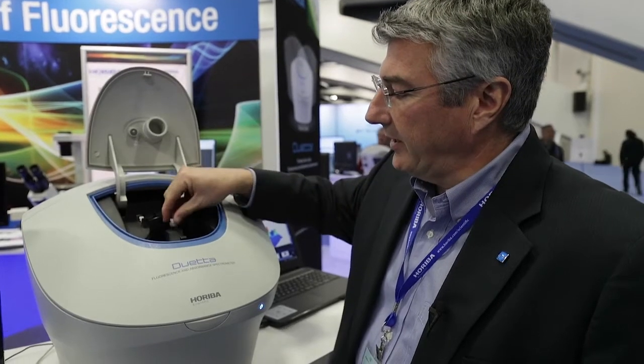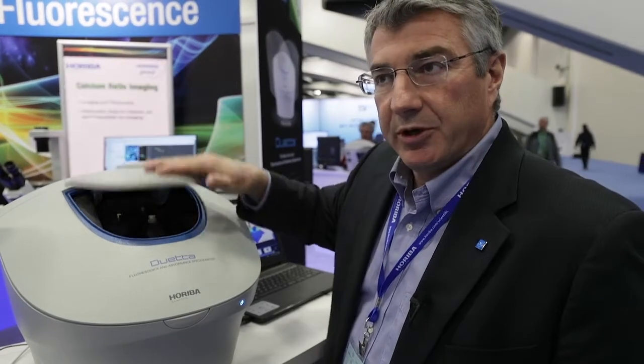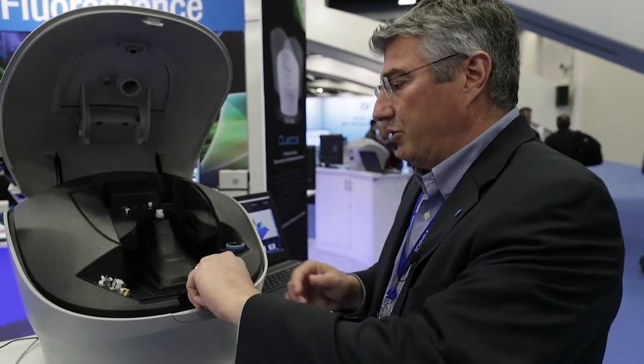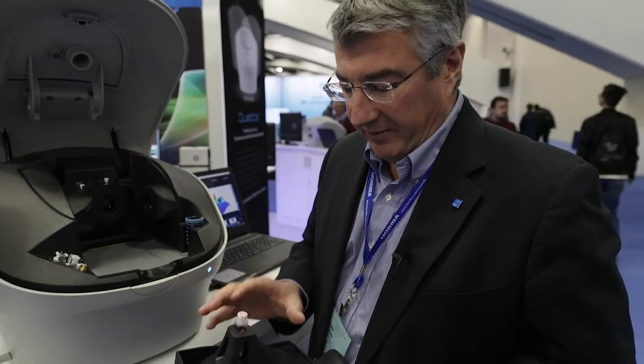The sample compartment for Duetta is here — I can press this lid down and replace the sample for my next experiment. But sometimes we want to use a different kind of sample holder altogether, so we open the main lid and can remove the sample tray. We have many different sample trays: trays for controlling the temperature of the sample, a four-position sample holder, solid sample holders, powder sample holders — many different kinds of trays can be put inside the unit.